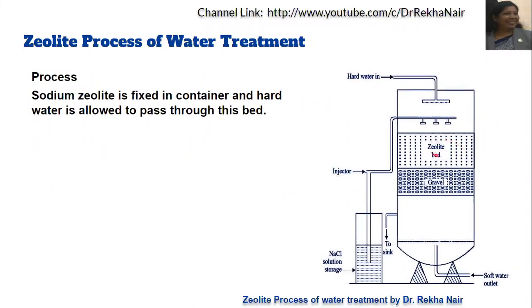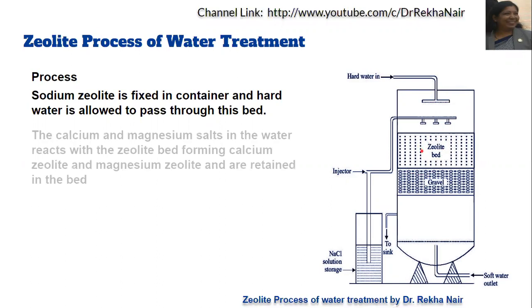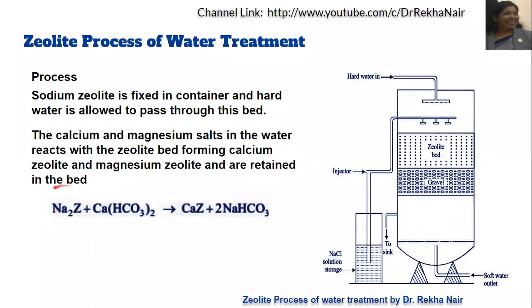The sodium zeolite is fixed in the container and hard water is allowed to pass through this bed. The calcium and magnesium ions — that is, the hardness-producing salts present in the water — will react with the zeolite bed, forming calcium zeolite and magnesium zeolite, which are retained in the bed. The softened water is then filtered through the gravels and drawn out. We have the reactions as: sodium zeolite plus calcium ions present in the hard water — let us take calcium bicarbonate.